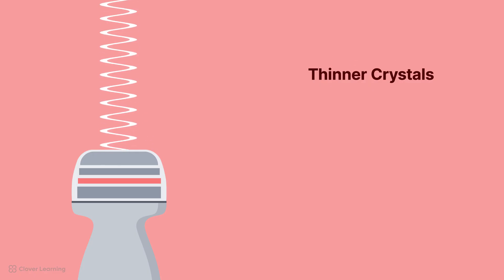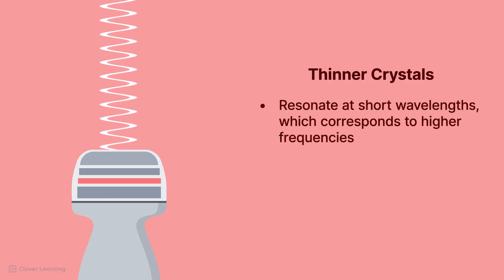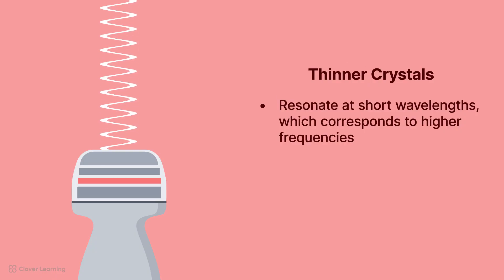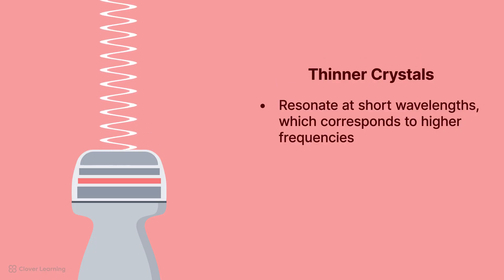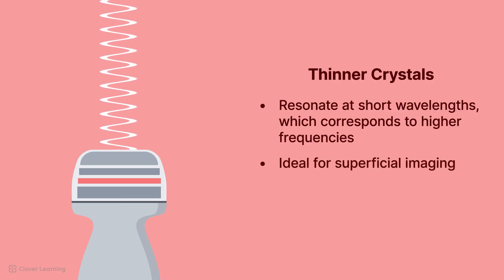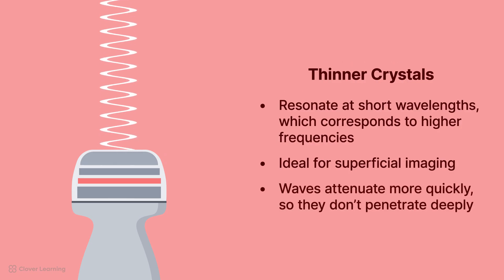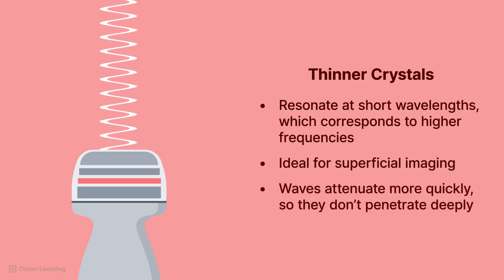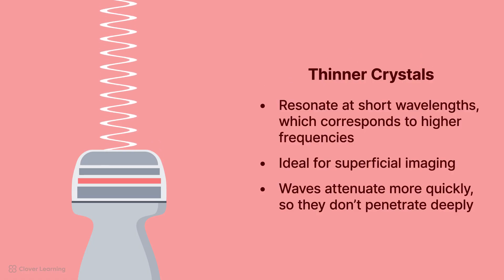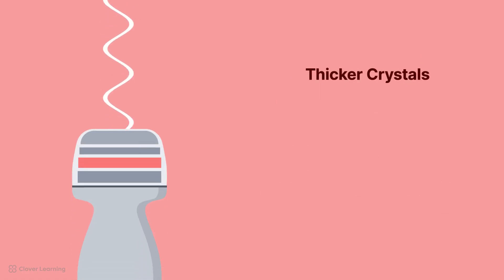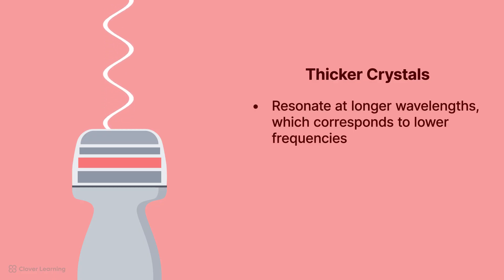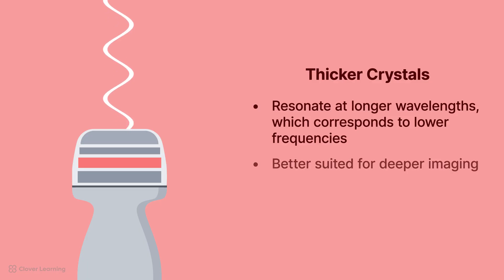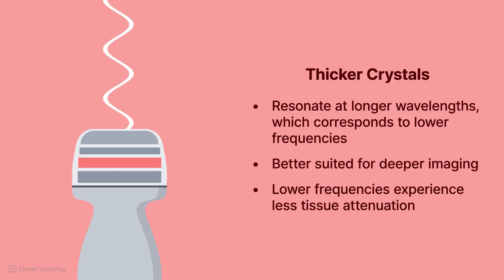A thinner crystal has a smaller physical size and naturally resonates at shorter wavelengths, which corresponds to higher frequencies, making thinner crystals ideal for imaging superficial structures like the thyroid. However, these waves also attenuate more quickly, meaning they don't penetrate deep into tissue. A thicker piezoelectric crystal has a larger physical size, so it resonates at longer wavelengths, which corresponds to lower frequencies, making it better suited for imaging deeper structures like the liver or kidneys because lower frequencies experience less tissue attenuation.